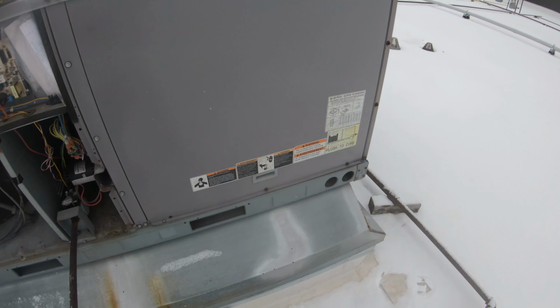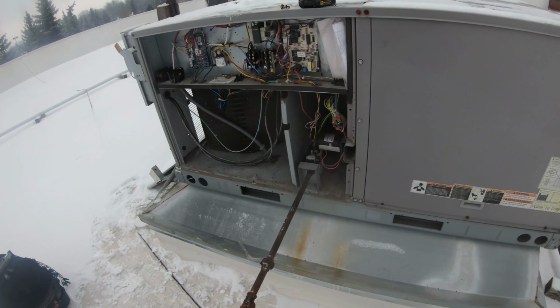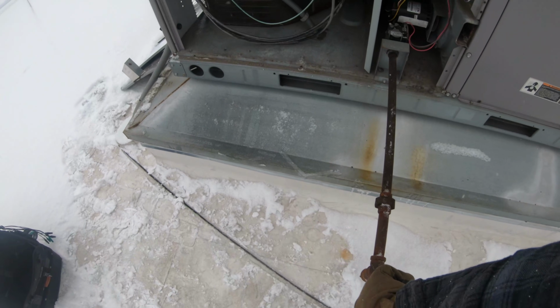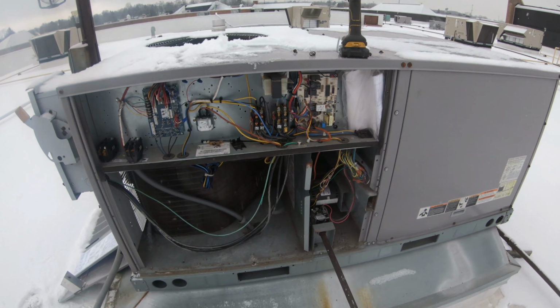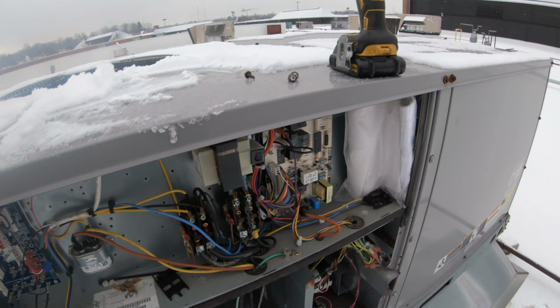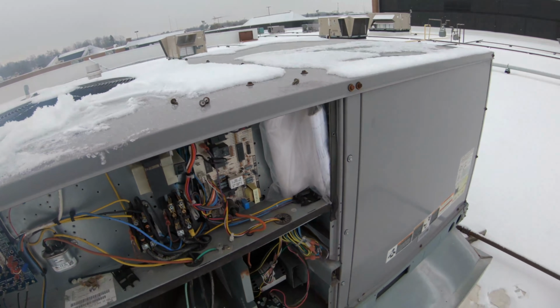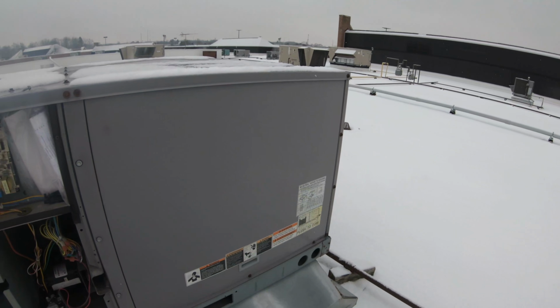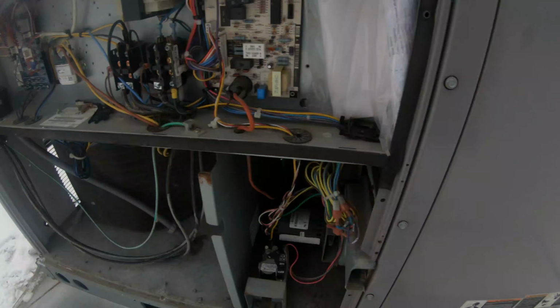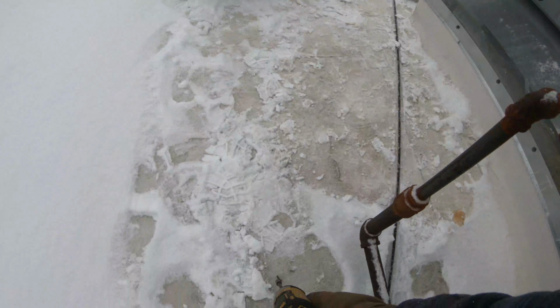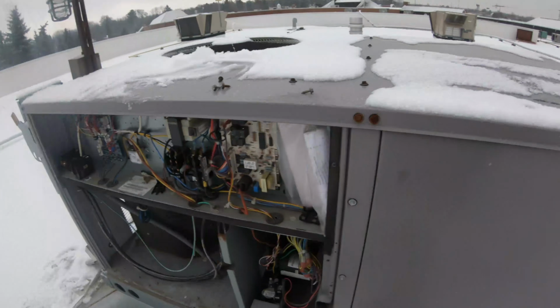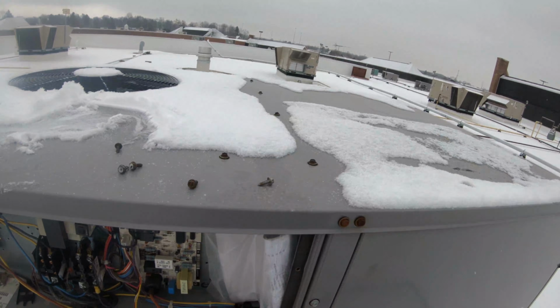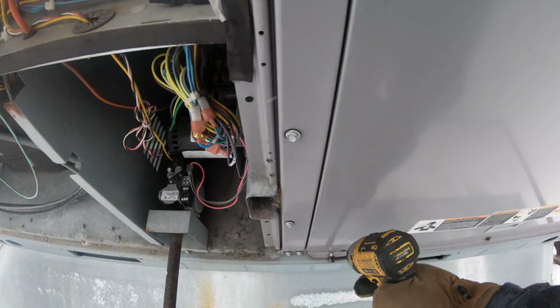Blower is running. We'll go ahead and shut this gas off so that heat exchanger doesn't get too hot. Let it cool down. We're gonna inspect this heat exchanger right off the bat, because you guys know as well as I do, these carriers, at least half the time, have got a crack in them.